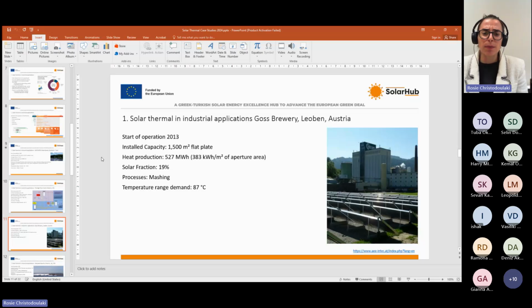Now, continuing the industrial applications, we have a brewery, the Goss Brewery. It is quite renowned in Austria. The solar thermal system started its operation in 2013. It consists of 1,500 square meters of flat plate collectors, and it can produce heat of 527 megawatt hours per year.